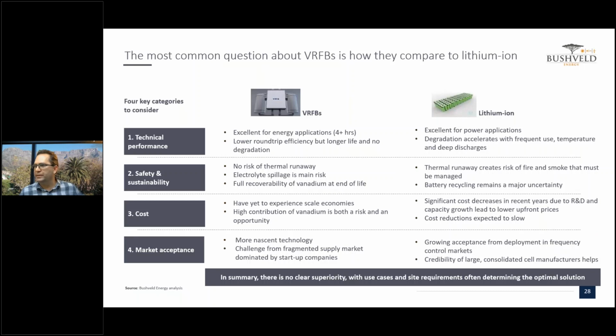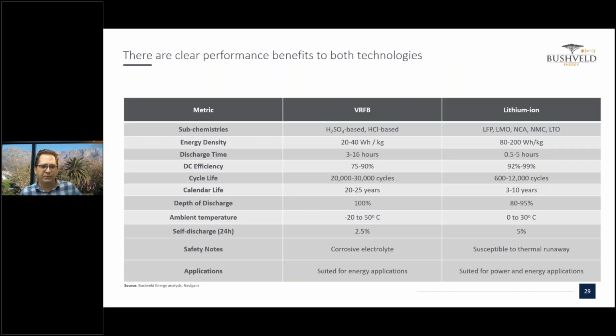I'm not going to go into all the details here, but comparing VRFBs to lithium, VRFBs are really well suited for long duration applications. They have the value that power and energy are decoupled, because the stack sets up the power, or megawatt rating, of the battery, while the quantity of electrolyte sets up the megawatt hours, or duration. I think the long duration nature and lack of degradation, when you do an LCOE comparison versus lithium that's regularly augmented, can give very good results.